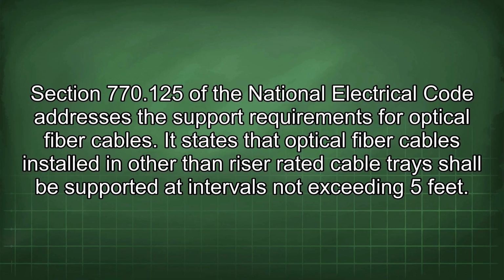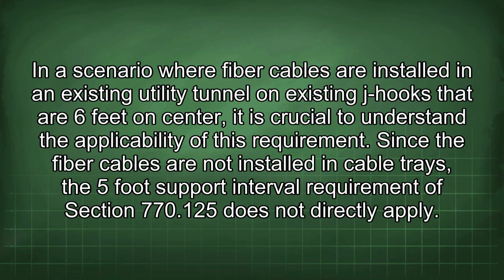Section 770.125 of the National Electrical Code addresses the support requirements for optical fiber cables. It states that optical fiber cables installed in other than riser-rated cable trays shall be supported at intervals not exceeding 5 feet. In a scenario where fiber cables are installed in an existing utility tunnel on existing J-hooks that are 6 feet on center, it is crucial to understand the applicability of this requirement. Since the fiber cables are not installed in cable trays, the 5-foot support interval requirement of Section 770.125 does not directly apply.